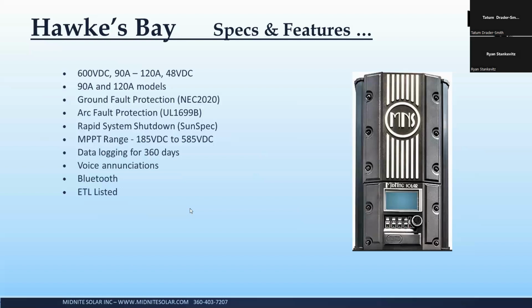So we're actually installing 12 Hawke's Bays in place of the 24 60 amp MPPTs. And that's just something we've always worked towards: what happens if there's a catastrophic issue and a battery goes away or something like that? Our systems regulate very, very rapidly. And as such, when the battery goes away, you just won't see that spike like you do on some other charge controllers, where the battery voltage will run out of sight and it blows the capacitors internally. So that's kind of a nice feature. It's all safe. We're going to talk about another safety feature in a minute.